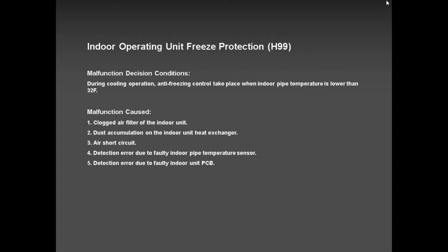The good thing about the H98 is that it's a hidden error. It's an error that will not shut down the system unless the indoor unit is super dirty. If the indoor unit is super dirty and the filters are completely clogged, then the system will shut down. But if the system is shutting down because you're using fewer indoor units, H98 will not trip that unit. It will be hidden. If you go and scroll, you might see it there, but the unit is still operating.